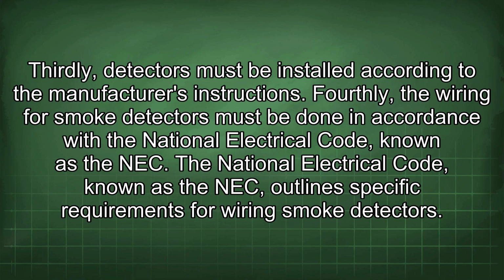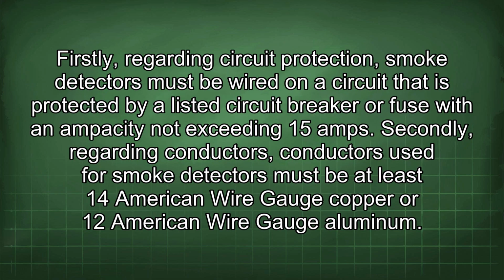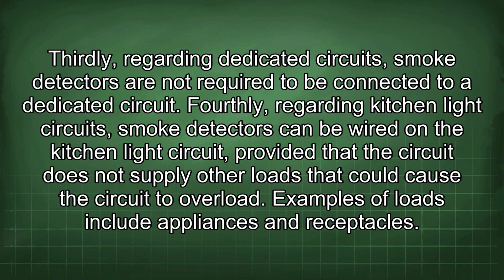The National Electrical Code, known as the NEC, outlines specific requirements for wiring smoke detectors. Firstly, regarding circuit protection, smoke detectors must be wired on a circuit that is protected by a listed circuit breaker or fuse with an ampacity not exceeding 15 amps. Secondly, regarding conductors, those used for smoke detectors must be at least 14 American wire gauge copper or 12 American wire gauge aluminum. Thirdly, regarding dedicated circuits, smoke detectors are not required to be connected to a dedicated circuit.